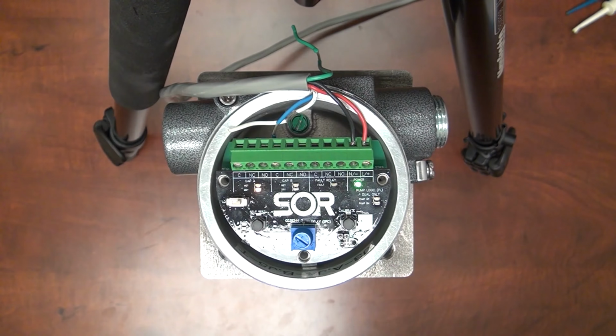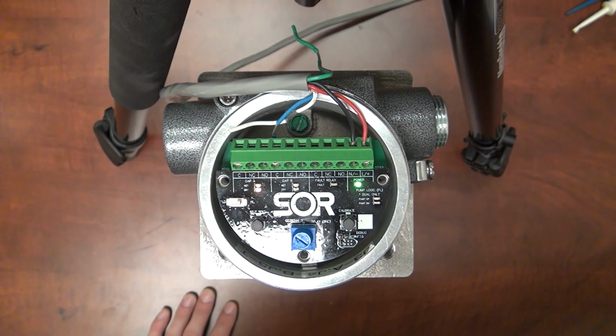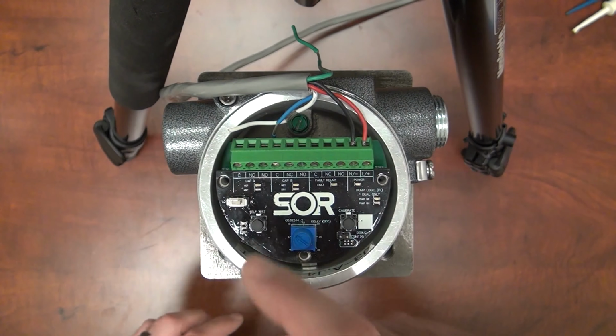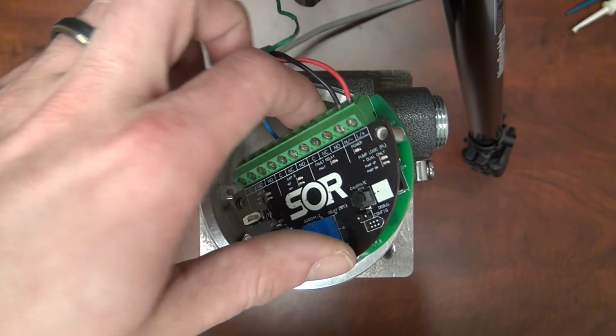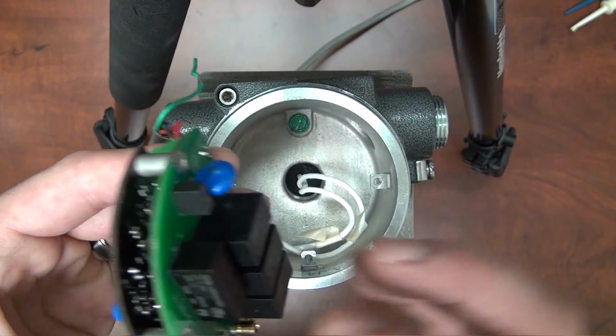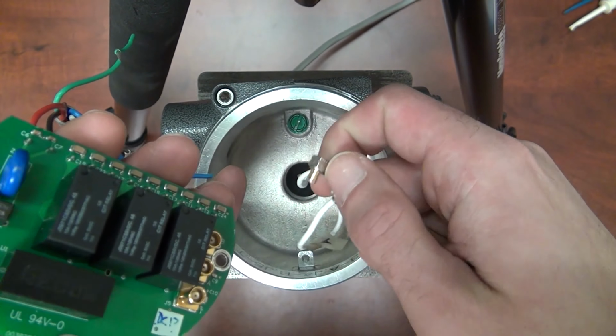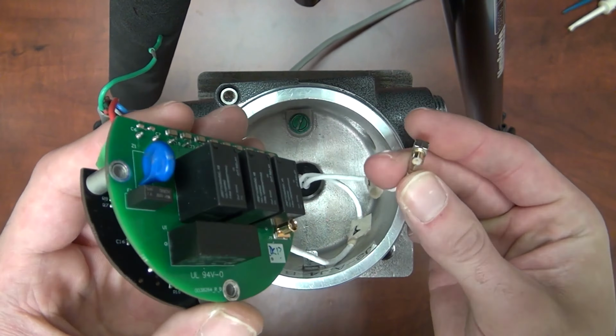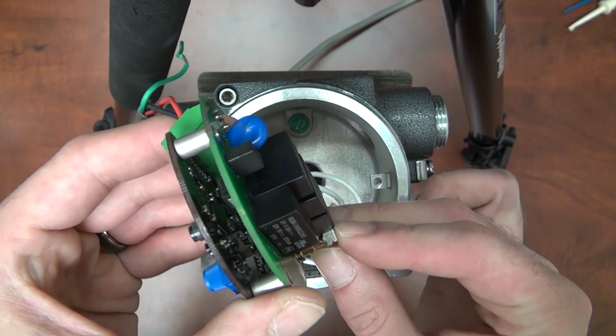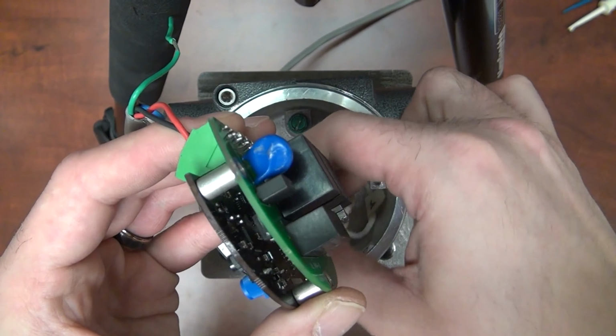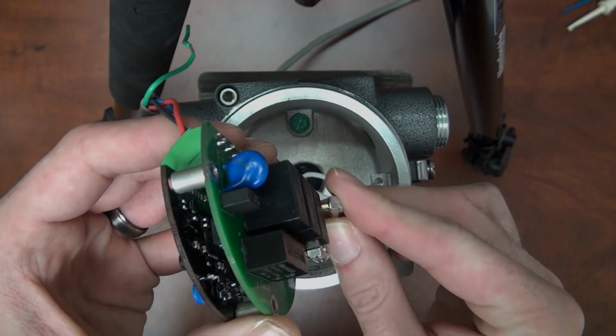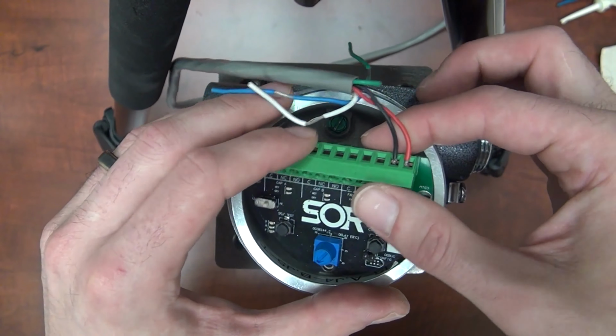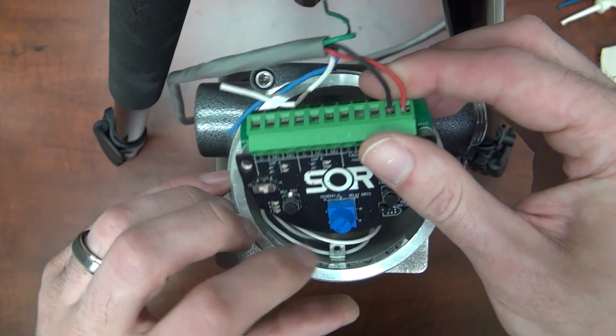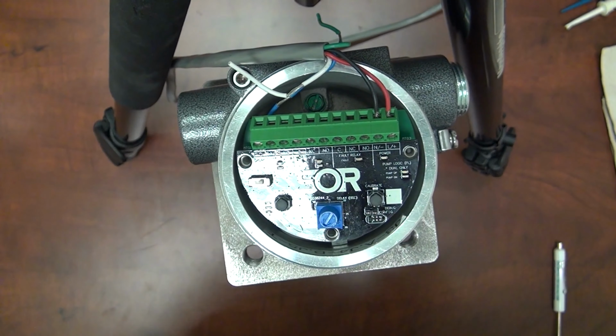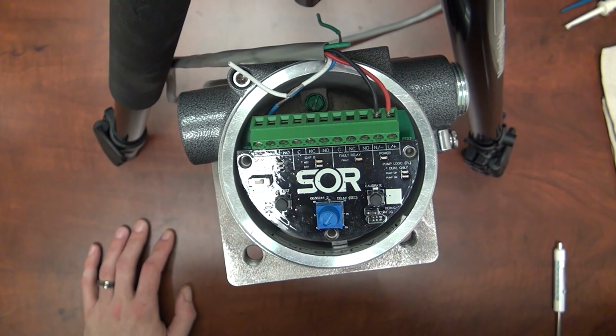Next, let's perform the dry sensor calibration. To start, remove power from the device. Remove the 3 screws and gently disassemble and remove the interface and power board. Ensure that the probe connectors are connected to the back of the board, with the correct cables going to the correct connectors with the labels. Now that we've reconnected the probe to the power board, we'll put it back inside the electronics housing.